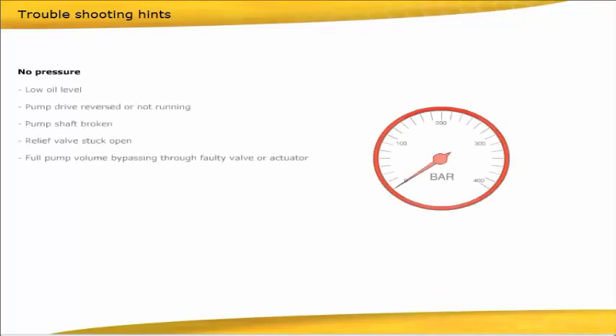No pressure. Low oil level. Pump drive reversed or not running. Pump shaft broken. Relief valve stuck open. Full pump volume bypassing through faulty valve or actuator.